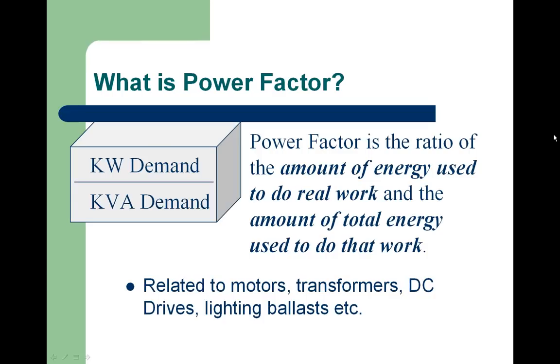Typically, utilities actually measure in kilowatts as well as kVAR, kVAR being inductive reactance. We're going to get a little further into it, but just to give you some idea of what things have good power factors: incandescent lights typically have a unity power factor. Motors typically have a power factor somewhere in the 80s to the high 80s, in motors less than, say, 300 horsepower, and that would be at full load.